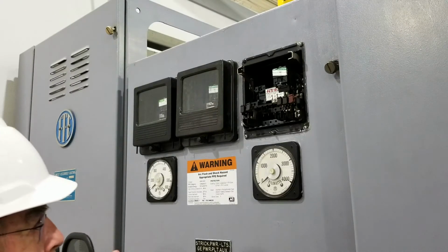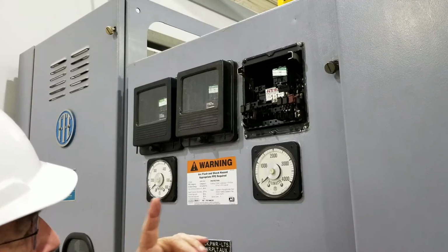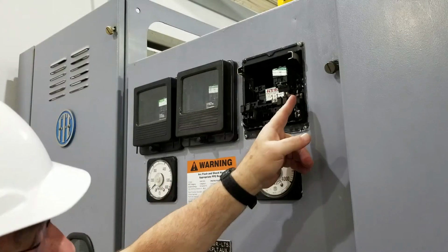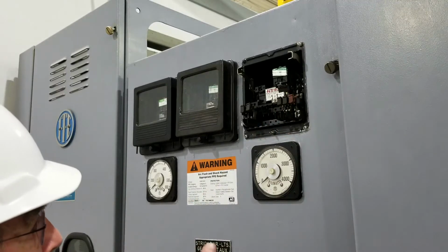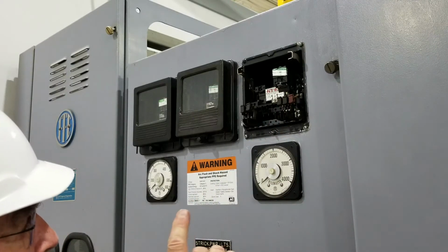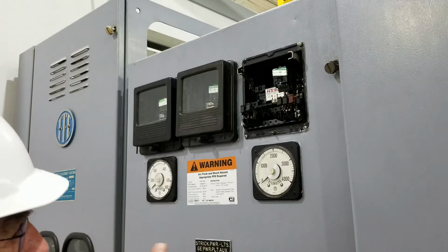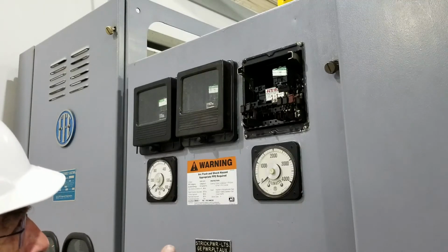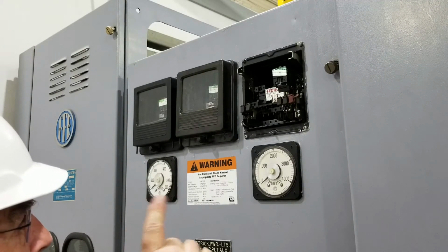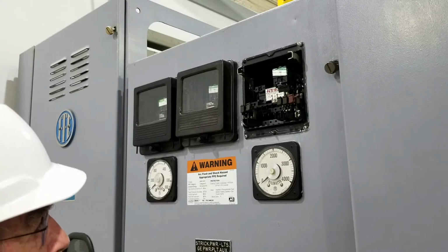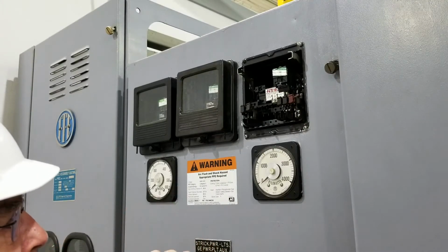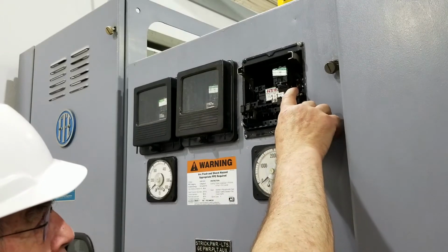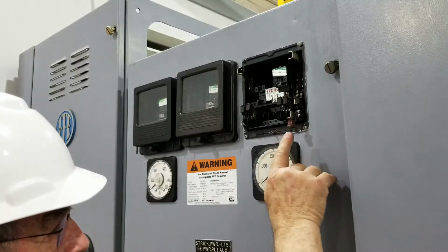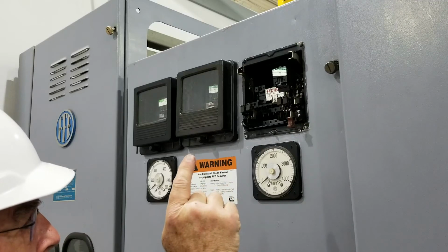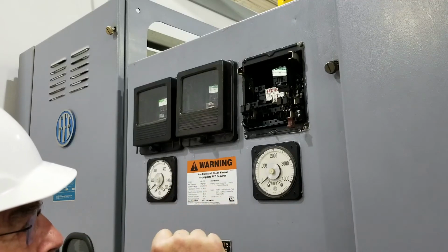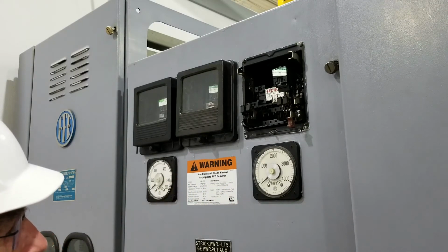Now, anyone who knows me and relays knows that I'm a stickler on this red handle switch here. That red handle switch is the key to making sure we cannot inadvertently trip the circuit breaker if the contacts of the sealing unit accidentally close. So the very first thing we do is open up that red handle switch. The moment we do that, we clear the trip circuit and nothing can happen as far as the circuit breaker is concerned.